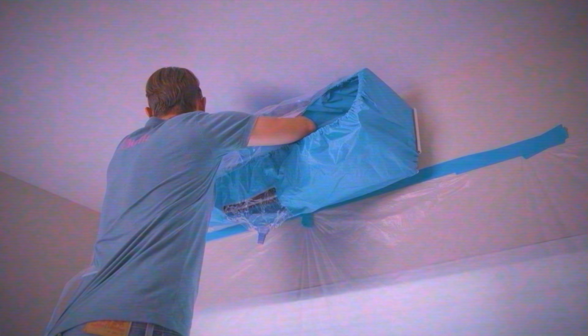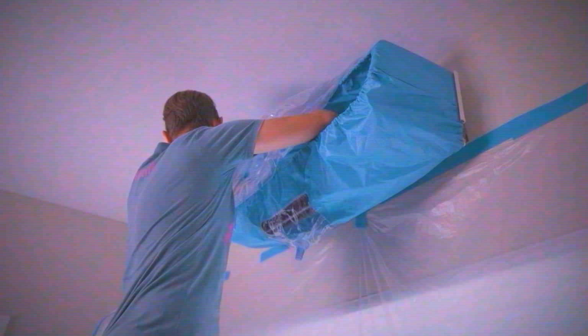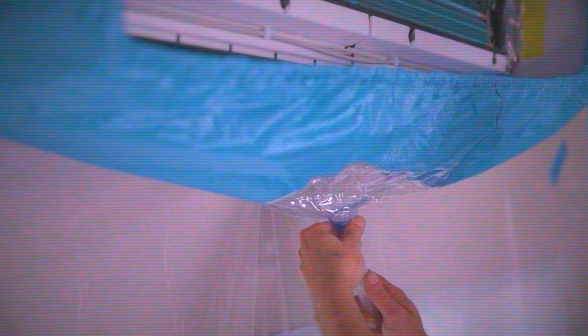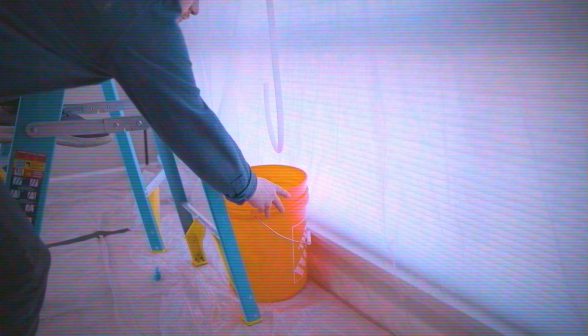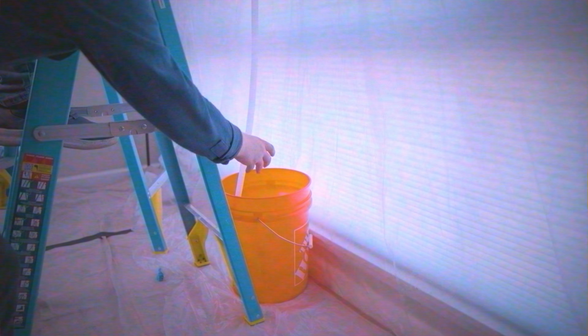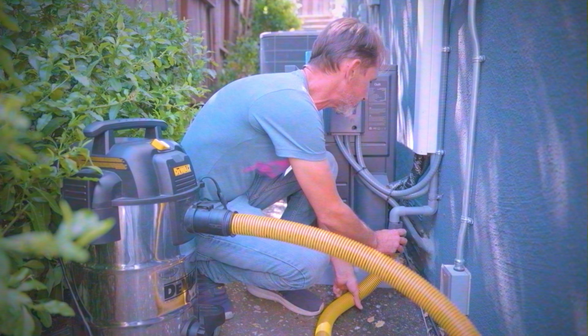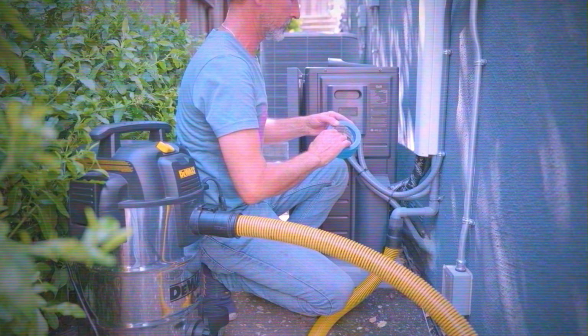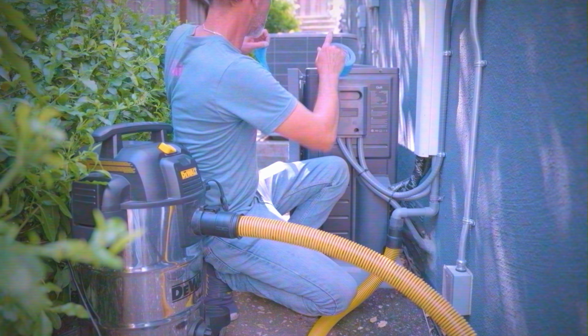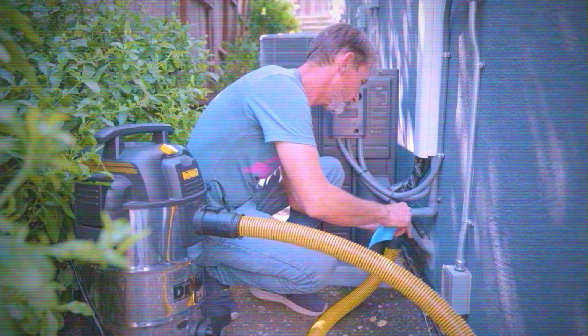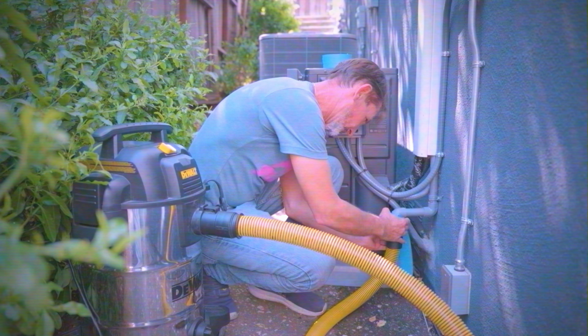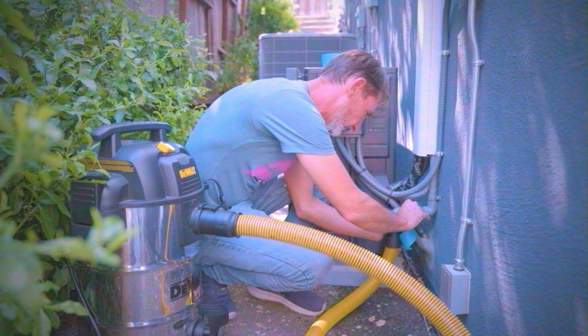Follow the product's instructions to secure it along the length of the unit. Make sure the drain port is angled downward, attach the drain hose, and run it to a floor drain or bucket. Next, set up and turn on the wet-dry vac. Head outside to the condensate line outlet. Attach the vacuum hose to its end. This will pull out excess moisture and prevent blockages in the line.